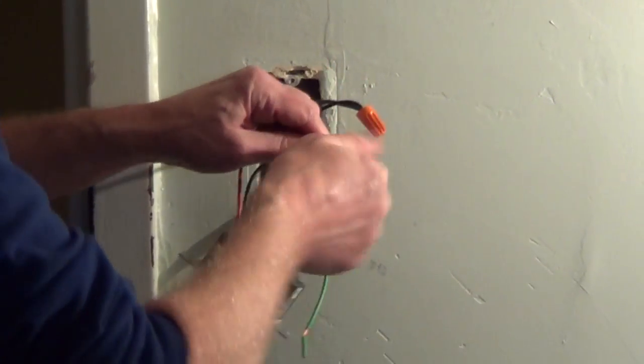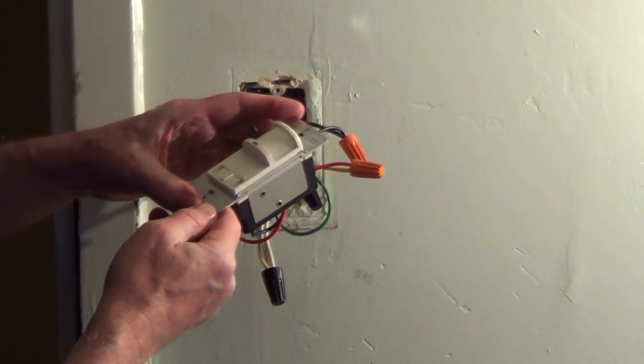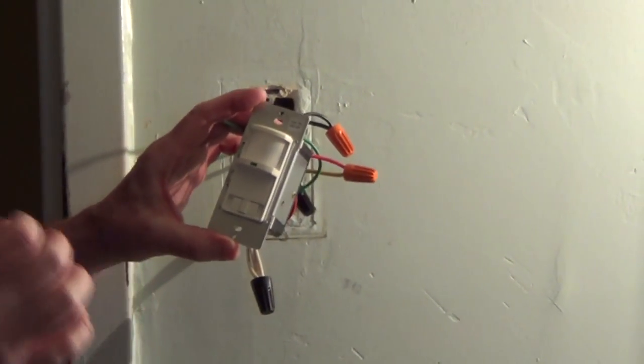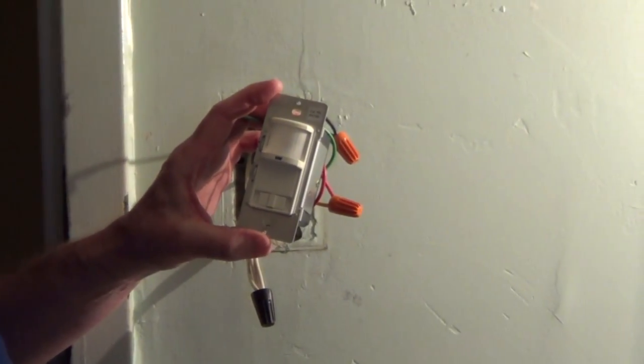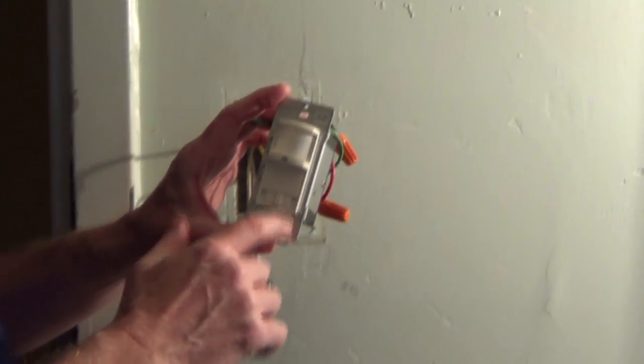And the only other thing that you want to know with a motion detector like this is how many watts it's rated for and this one is rated for 500 watts and you need to make sure that what you're drawing, so in this case we've got two 34 watt fluorescent bulbs and one 60 watt bulb.